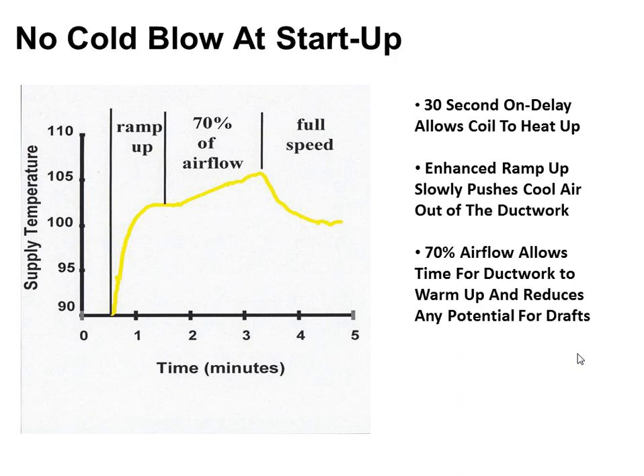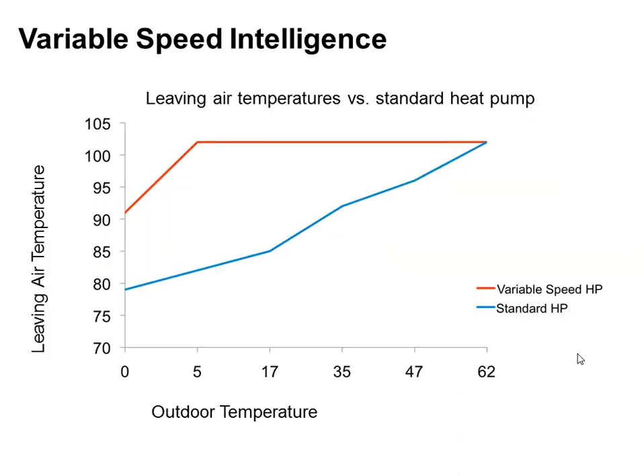It's kind of similar to what we do on gas furnaces now. We fire the burner, and then after things get warmed up, then we go ahead and turn on the airflow so you don't get that burst of cold air. So that's one thing that we do to help resolve that. The other thing that we do is try to maintain a higher operating discharge temperature for as long as possible.